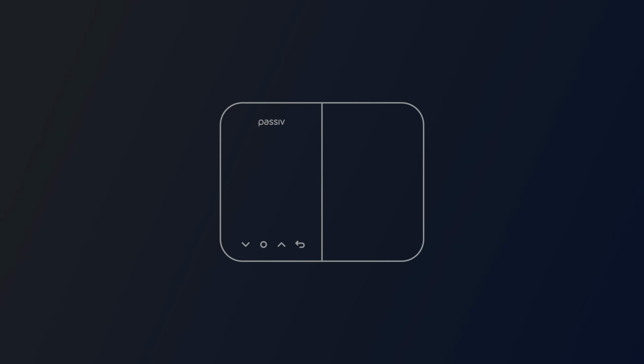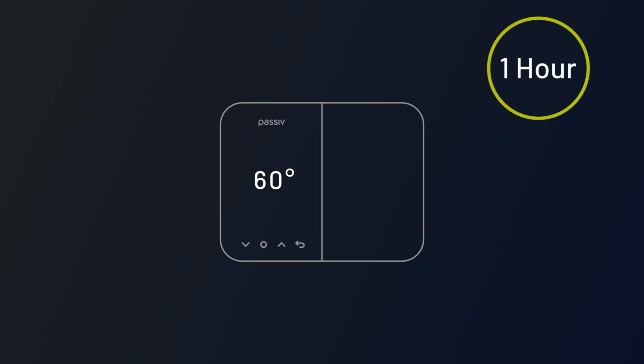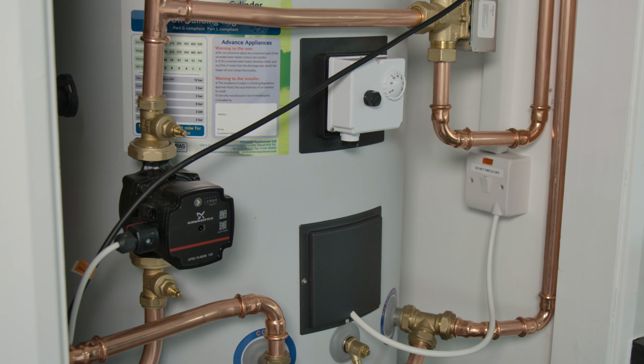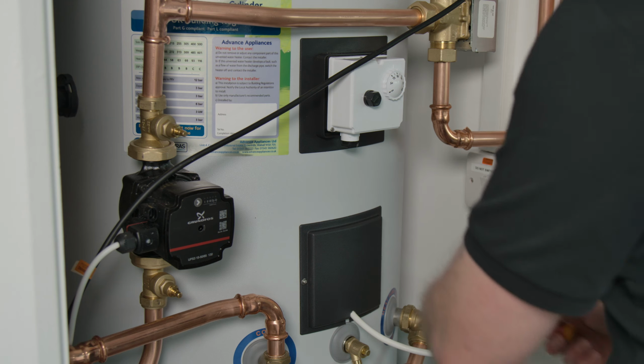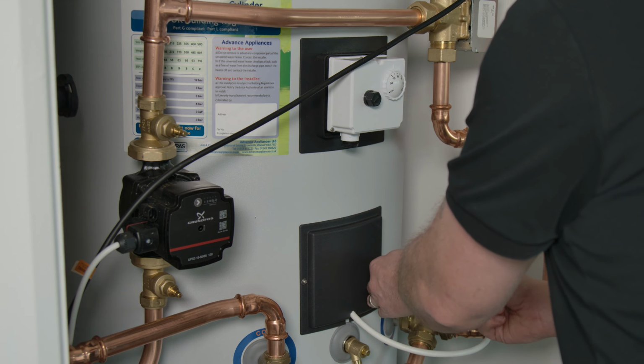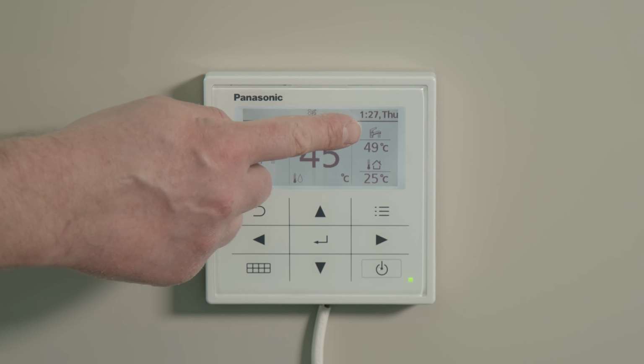Once you have started the immersion test, the cylinder temperature should start to rise. Let the test run until the cylinder temperature exceeds 60 degrees Celsius for at least an hour to ensure reliable and safe operation for anti-Legionella cycles. While the programmer will inform you of the tank temperature in real time, it is recommended to also check the tank itself to confirm that the temperature probe is providing reliable readings.